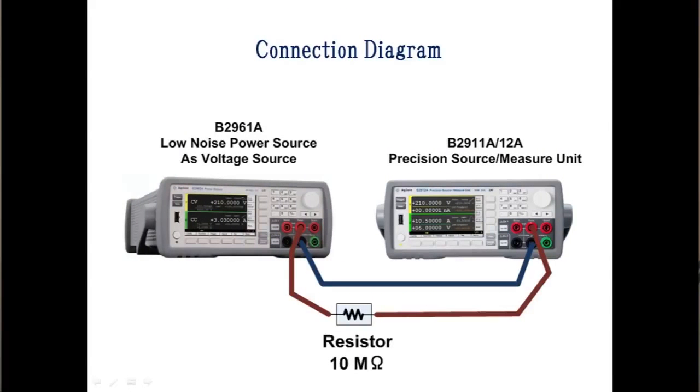Let's use voltage source with 10 mega ohm resistor at output to emulate device with large output resistance and measure voltage. This is the connection diagram. B2961A power source is used as voltage source and its high force terminal is connected to 10 mega ohm resistor, then high force terminal of SMU. Low force terminals of power source and SMU are connected directly.